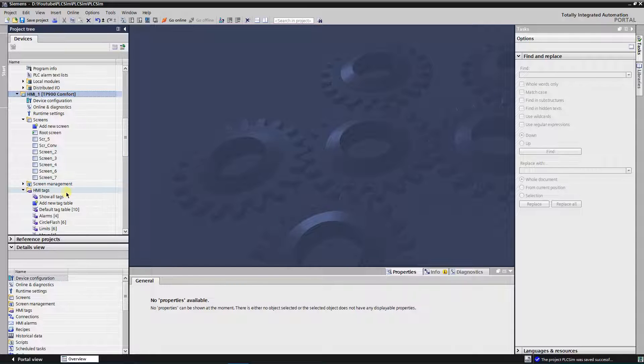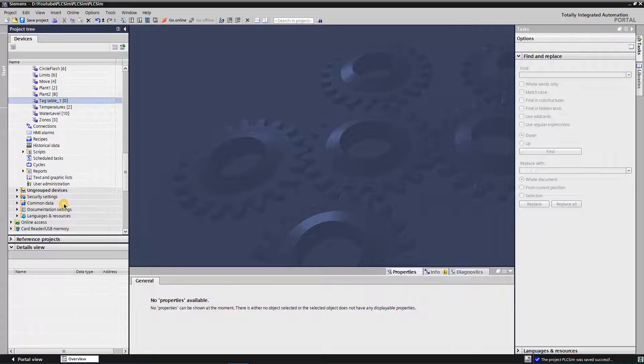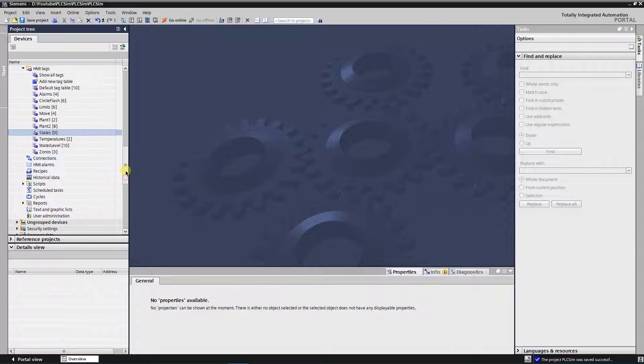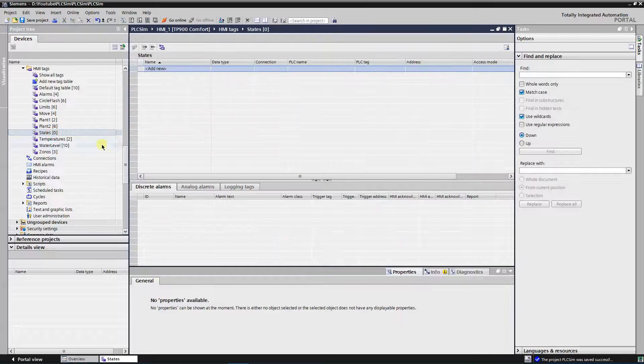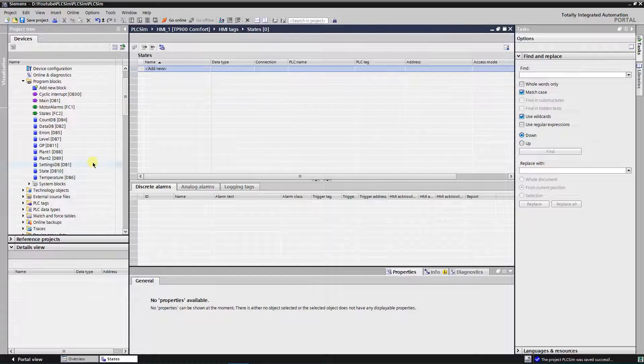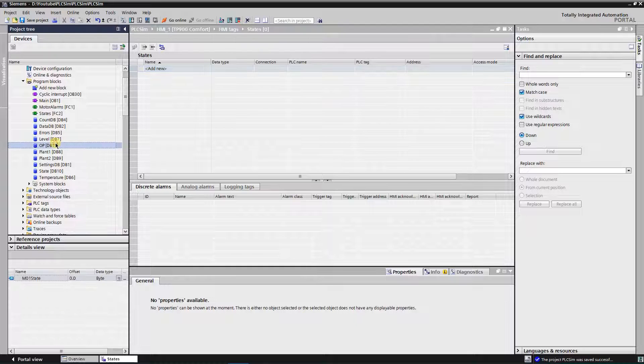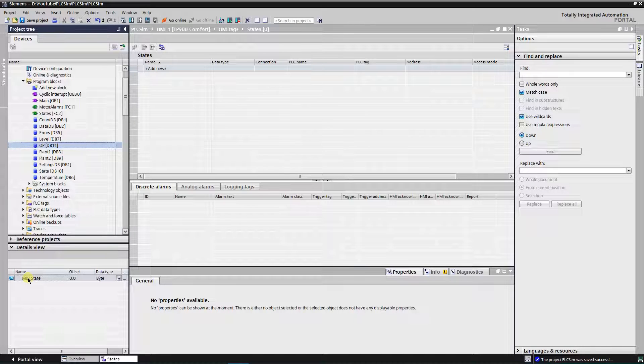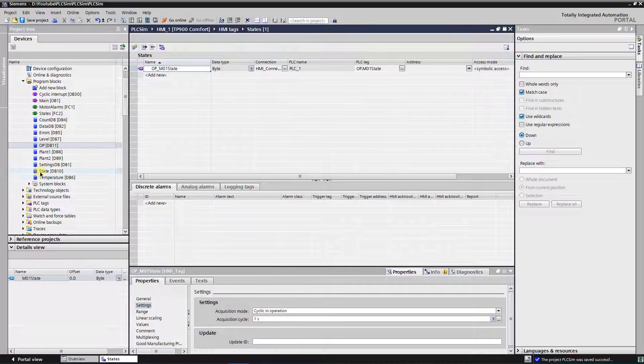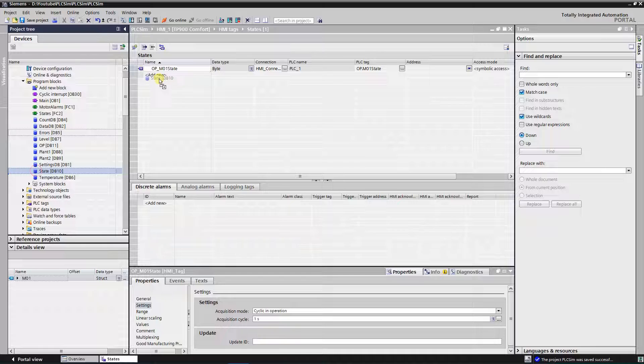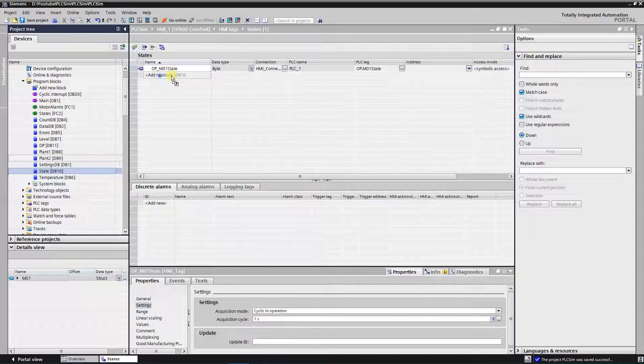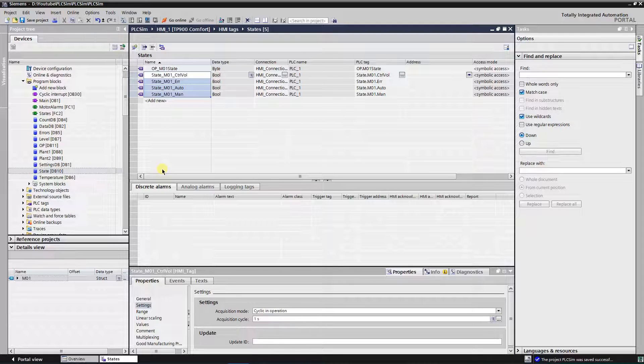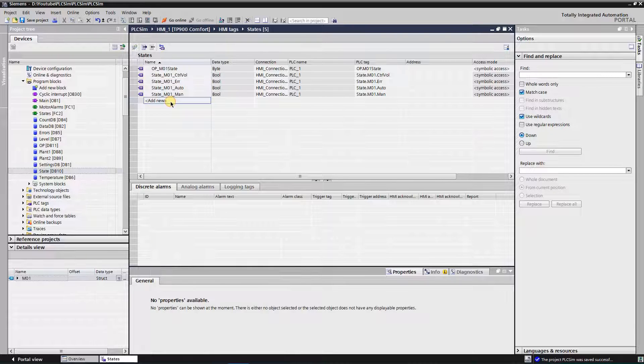Now let's create a visualization of the states of the motor. First I will configure the tags. Create a tag table in your HMI project and open it. In the project tree find the DB11 and mark it. Drag and drop state byte into the tag table of the HMI. In the project tree find the DB10 drag and drop it into the tags table of the HMI. All the tags from DB10 are now saved in the tag table of the HMI. Tags are done, switch to the screen.